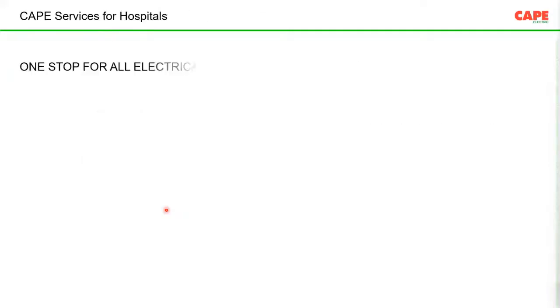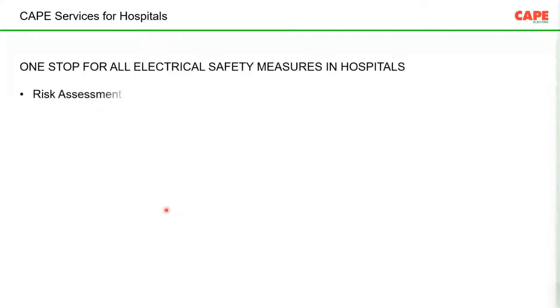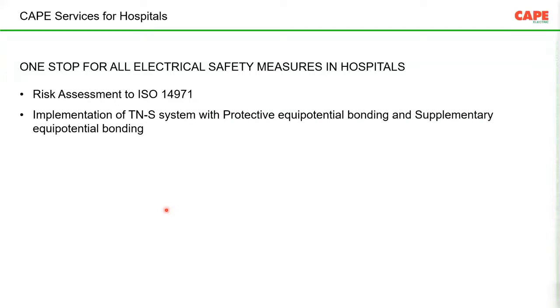Now, what we offer at CAPE, we are capable of offering the entire solution, starting with the risk assessment as per ISO 14971. In medical areas there are chemical things, biomedical things, and wastes, how to handle them, and how to solve issues in case of accidents are included in the ISO. In this particular ISO, you have to make a risk assessment. Then implementation of the TN-S system with the protective equipotential bonding and supplementary equipotential bonding. This we are doing already in several hospitals.